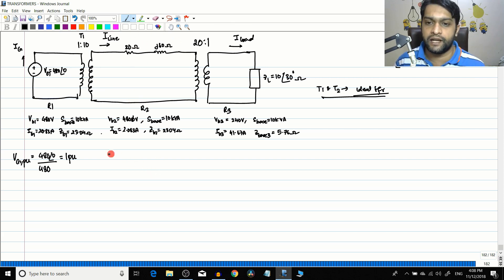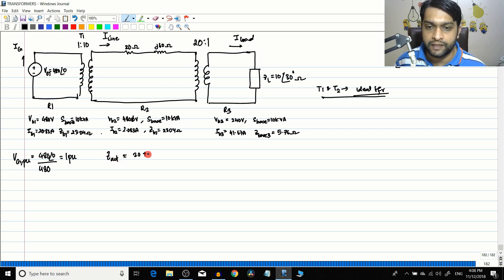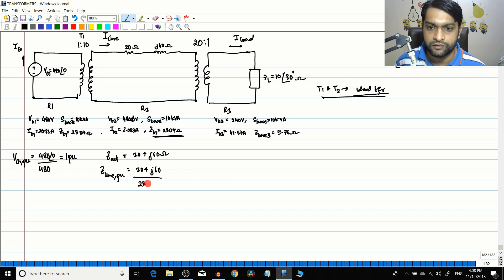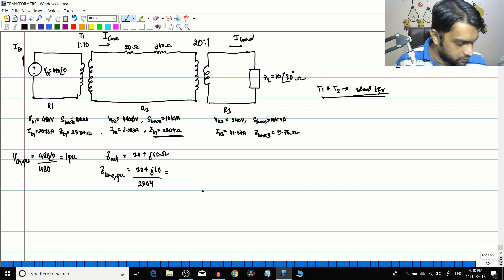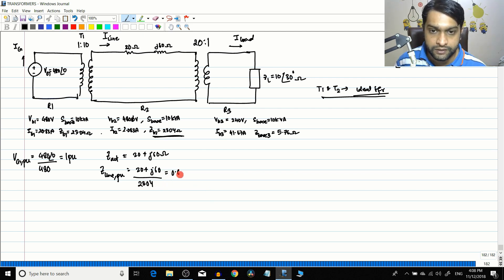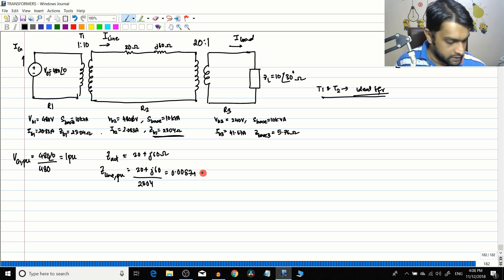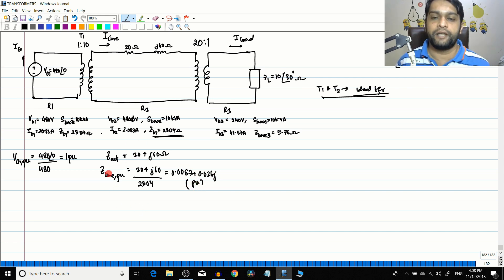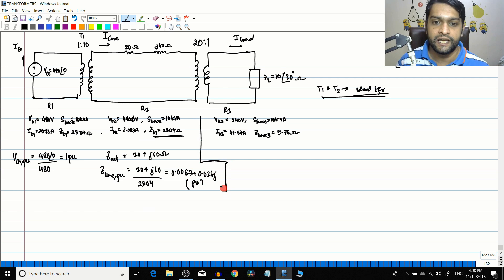Next we come to the transmission line. The actual impedance value is Z_actual = 20 + j60 ohms. So Z_line_pu equals the actual value divided by the base value: (20 + j60) divided by Z_base = 2304. This gives 0.0087 + j0.026 pu. Notice that per unit quantities are dimensionless because the actual value and base value share the same units, so they cancel out.